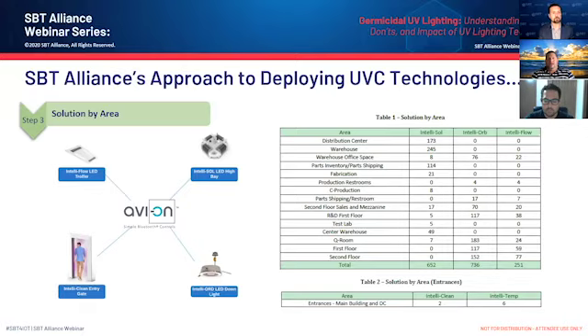So by having that understanding, we could quickly state that, okay, if we have to change, let's just say, the UV LED light source in the IntelliFlow every 17,000 hours, we don't have to try to estimate the length of time those fixtures are actually on. Our control system provides that information to us, provides us a countdown, and potentially even sends alerts when it's time to do some maintenance on the UV light source within the IntelliFlow, within the Soul, and within the Intelli-Orb. What it also does is there's another metric that helps us understand when we have to change filters within the IntelliFlow.